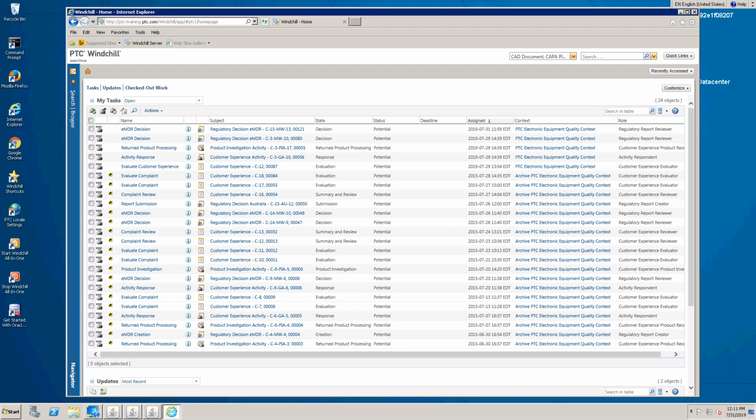So we have those additional options. We can go through and add a CAPA report that will say, okay, this is the corrective action or preventative action that was taken in order for this thing not to happen again. So maybe we changed manufacturing because the circuit board was bad, or it ended up being a bad batch, whatever it may be. So we can go through and now evaluate that information.